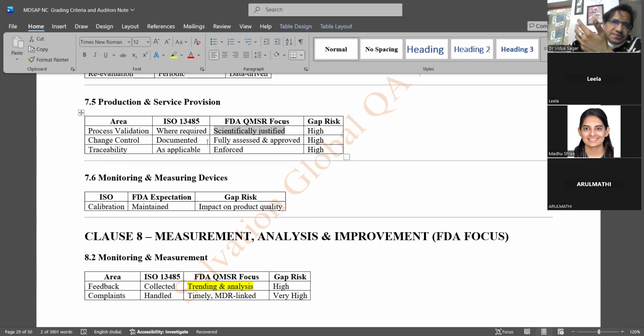When you don't use statistics in your data, from your sampling size, in your validation, how many samples you picked up, why you picked them up, what is the rationale? What is the statistics you applied? What is your confidence interval? What is your p-value, probability? What is the power of your study? A lot of things will come in. It has to be not only on the sampling side, it could be in your results. Your validation results are so and so. So you need to apply statistics to show why we need to apply statistics and all these p-values, because validations we conduct only once or twice in a year.